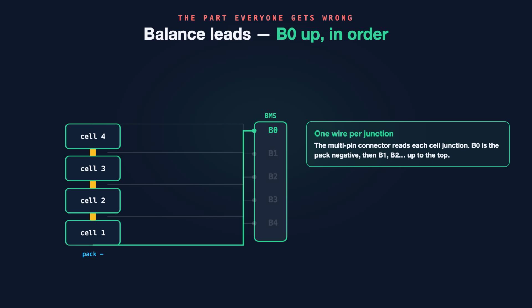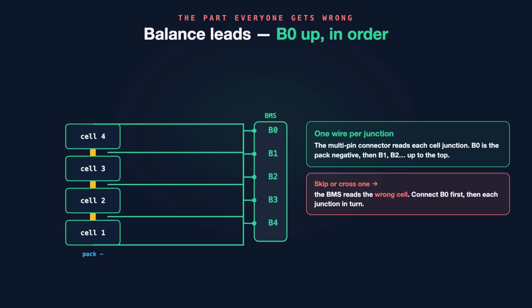Think of the taps as numbered from the bottom up. B0 is the pack negative. B1 is the joint between cell 1 and cell 2. B2 the next joint up, and so on, right to the top of the pack. The order is everything. You connect the balance leads from B0 upward, in sequence, bottom tap first, then each junction in turn. Get one out of order, or skip a tap, and the BMS reads the wrong cell, which can trip it, or worse. So go slow. B0 at the bottom, then B1, B2, up to the top. One wire, one junction, in order.